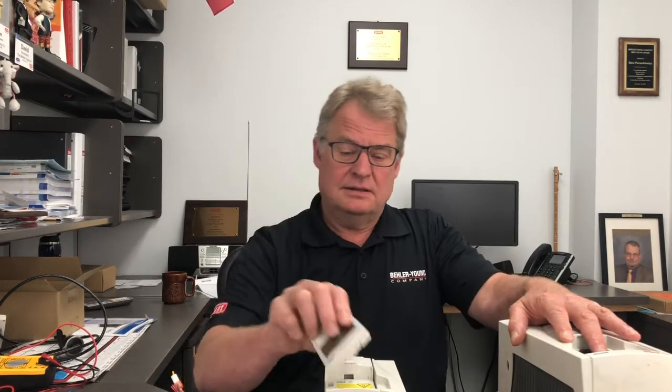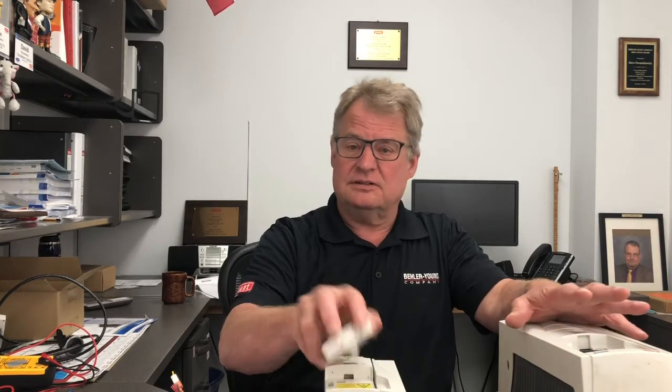On either drive, if we have a fault, we need to get the keypad, plug the keypad into the drive, recover the fault code, and determine what our issue is. Over voltage, over amperage, there's various different things. What we're going to focus on today is the hardware portion of this.